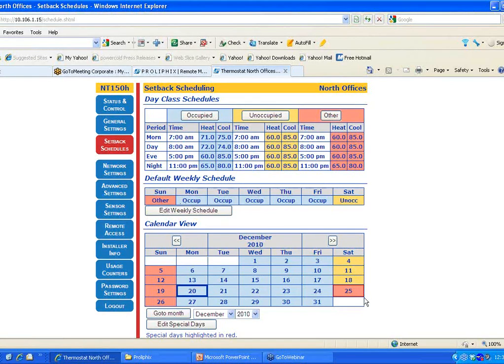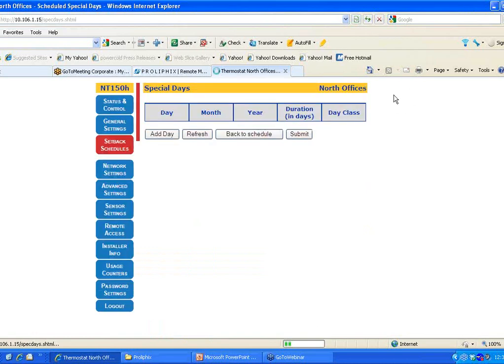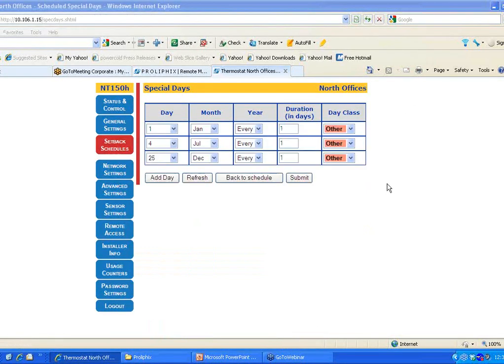However, you'll notice on Saturday, December 25th, which is Christmas, it's actually not following yellow. It's going to follow pink. That's probably because we have a special day configured for that as a holiday. In this case, it happened to fall on a Saturday, so it didn't really matter. It would have been in setback either way. But if it didn't fall on a Saturday like last year, then it would have been flagged on a Friday. So those special days override whatever normally would have happened on that day. So you can see here, we'll see what special days he has set up in here.